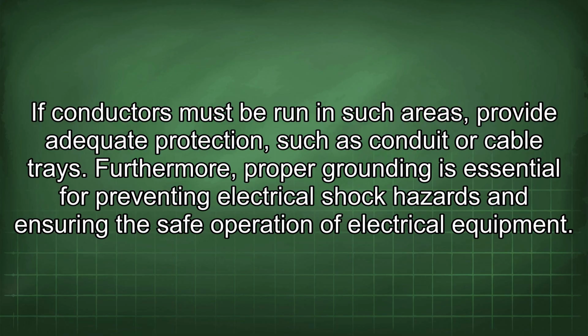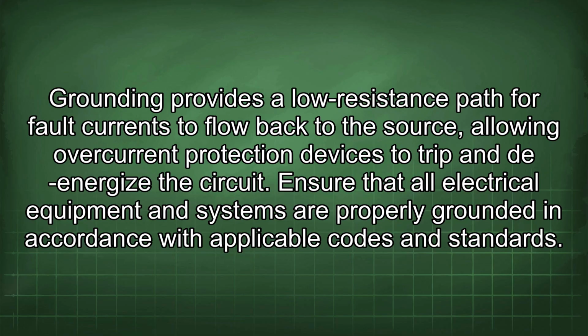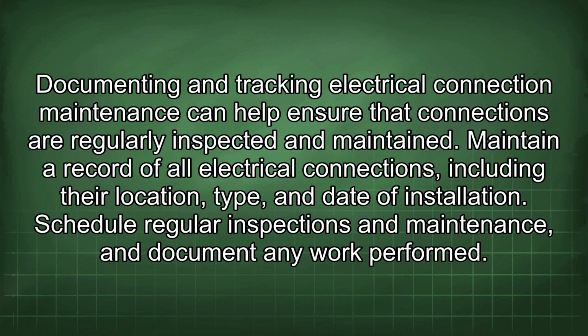Furthermore, proper grounding is essential for preventing electrical shock hazards and ensuring the safe operation of electrical equipment. Grounding provides a low-resistance path for fault currents to flow back to the source, allowing overcurrent protection devices to trip and de-energize the circuit. Ensure that all electrical equipment and systems are properly grounded in accordance with applicable codes and standards. Documenting and tracking electrical connection maintenance can help ensure that connections are regularly inspected and maintained.